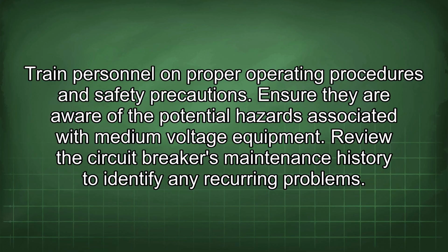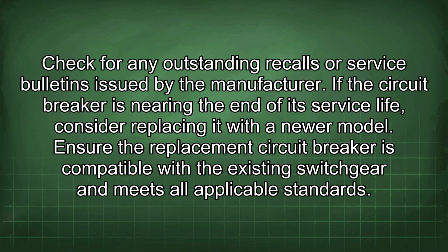Review the circuit breaker's maintenance history to identify any recurring problems. Check for any outstanding recalls or service bulletins issued by the manufacturer. If the circuit breaker is nearing the end of its service life, consider replacing it with a newer model. Ensure the replacement circuit breaker is compatible with the existing switchgear and meets all applicable standards.